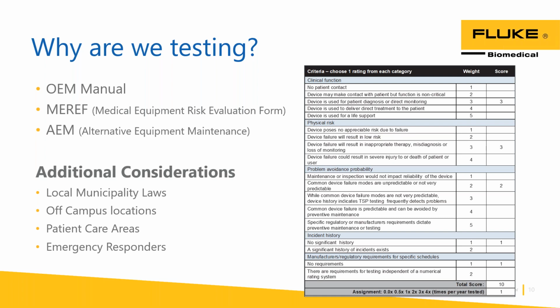There's another variance we can discuss. In the AEM, or in that OEM manual, it might list some sort of electrical safety testing, and in that manual it might call out a standard like IEC 62353, but we're actually testing to NFPA 99 in our facility. So are we actually following that OEM manual, or do we accidentally flip ourselves into an AEM without even catching it?